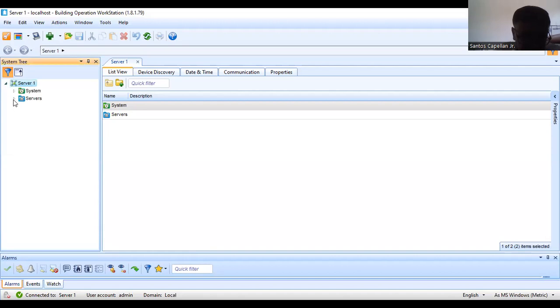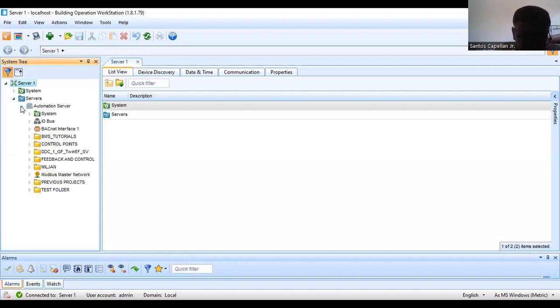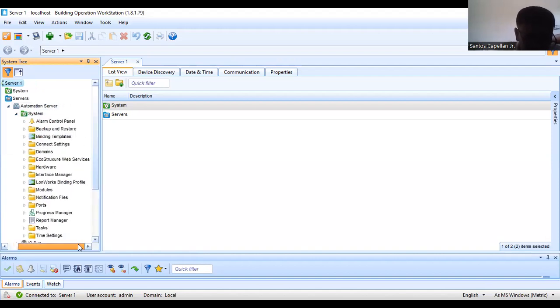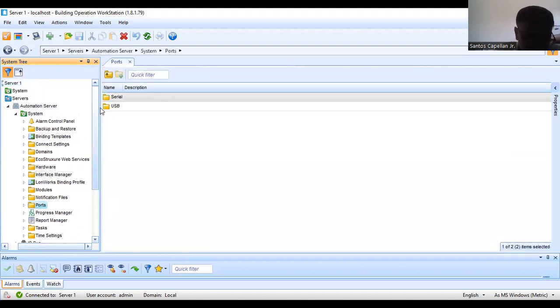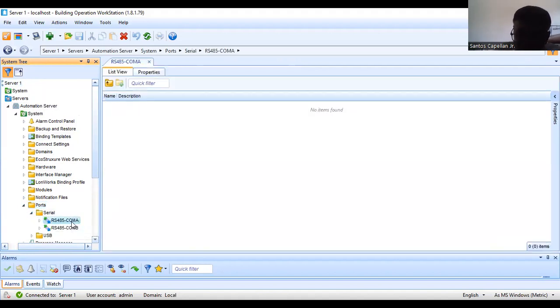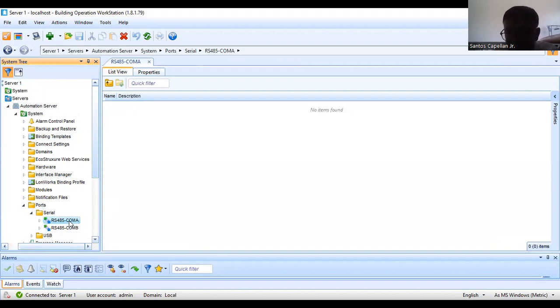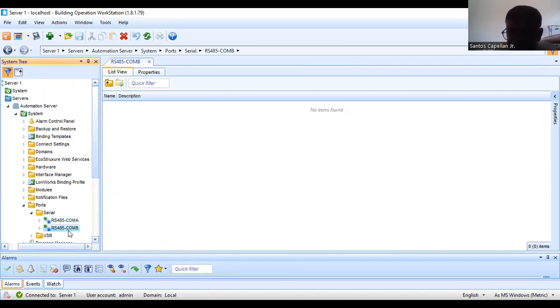This is my system where we will do third-party software integration. I have my automation server with serial port communication port A, dedicated to my BACnet MSTP controllers, and communication port B — this RS-485 port — which I will be using for our third-party BMS software integration.